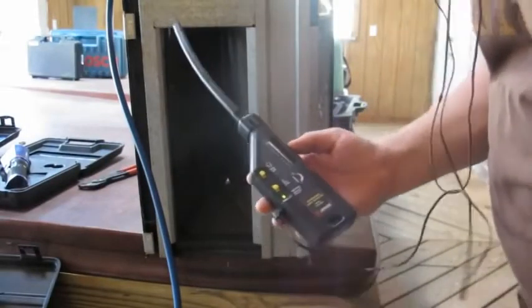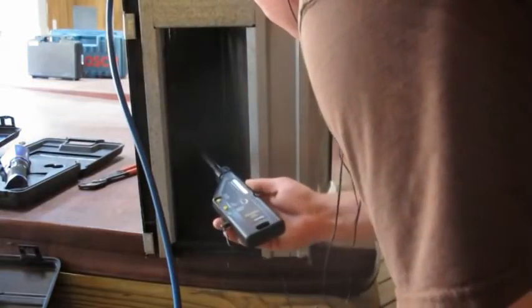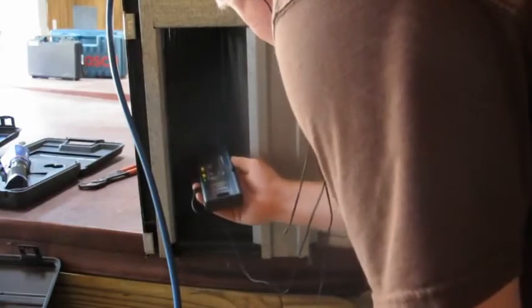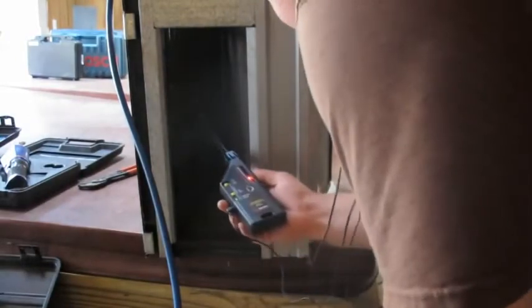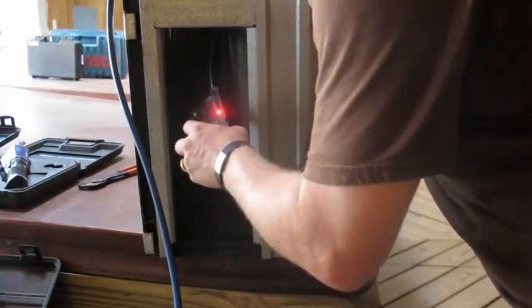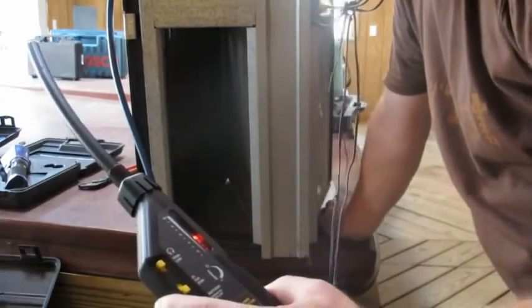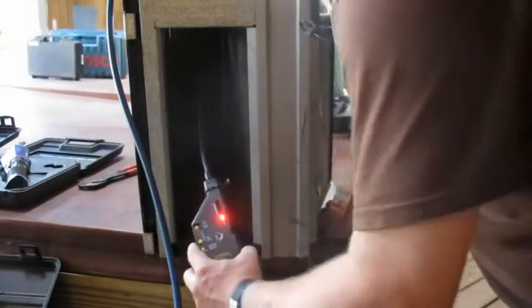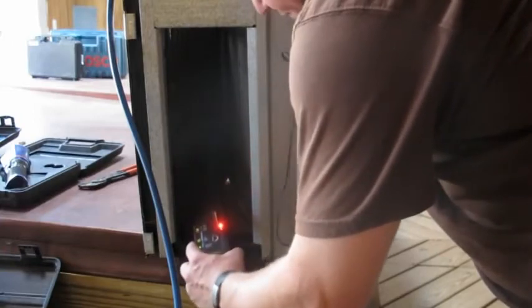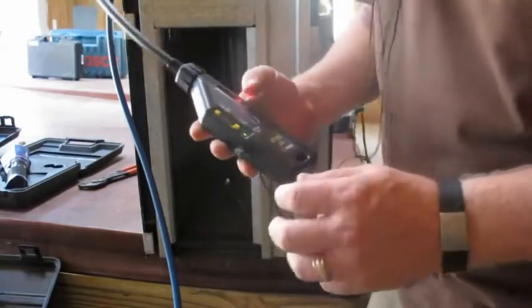Now I'm going to try the ultrasonic and see what it picks up. I've got the headphones on. I'm not hearing anything. I turned it all the way up. If you touch this on anything it's just real sensitive, but I hear no difference running along that coil. This is the Amprobe ULD-300 — I'm not that impressed, I don't hear anything.